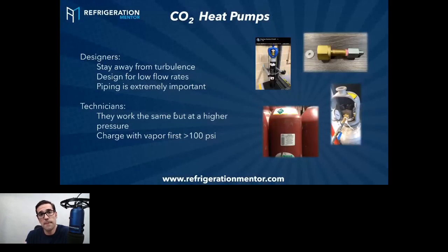But before you put liquid into that, because now you've got a good tight system, now you're going to add your charge in there. You need to add vapor first, like I said earlier. We need to get above that triple point. Say we put 100 psi or 150 psi or 10 bar of CO2 vapor. Then we put the liquid, and then we can start charging the liquid. On the smaller systems, it's a very small charge. But when you get to a larger commercial or industrial heat pump, that's where you could have hundreds of pounds of CO2, even thousands of pounds of CO2 in the system. So you really want to understand how it's done.